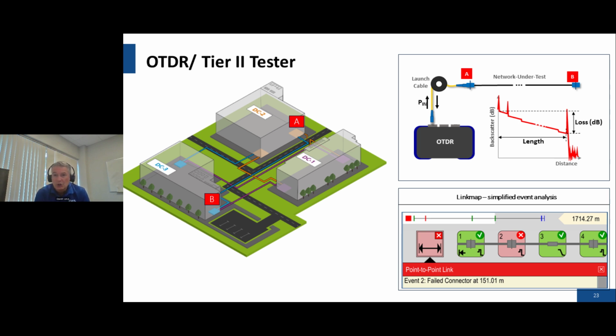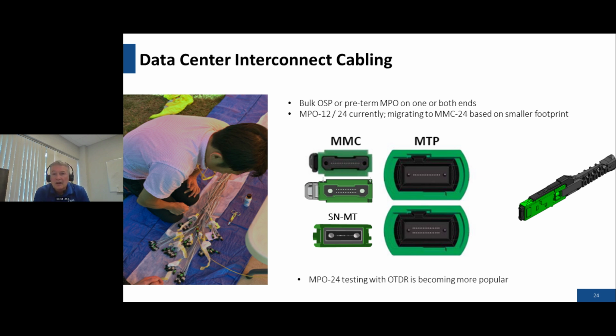In earlier versions of this product, it was pretty complicated sometimes to read what the trace looked like. The newer versions provide a very easy to interpret link map, which identifies the different types of events - connectors, splices, and so on. With the thresholds that can be set on each of these events, it will indicate whether or not the events were good or need to be redone. So significant improvement on those.